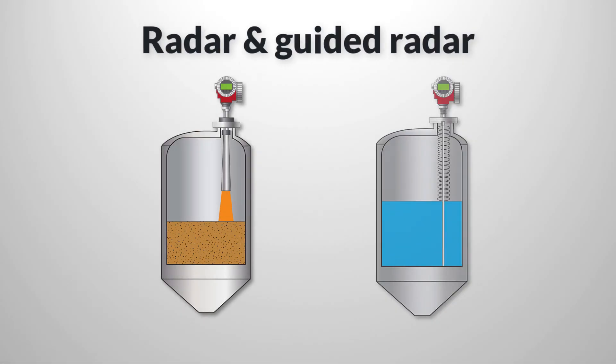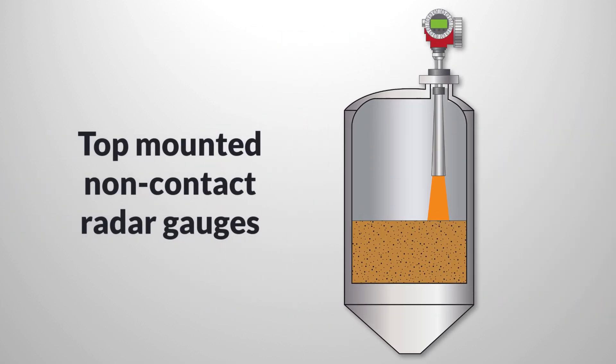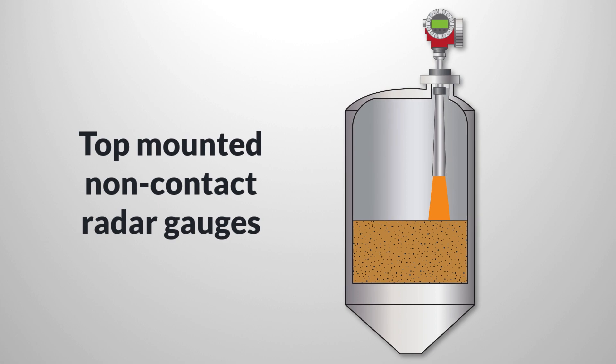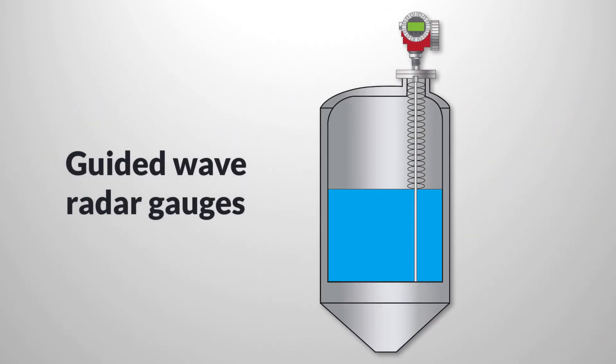Radar gauges are among the most versatile at a price. Radar gauges come in two variations. Top-mounted, non-contact radar gauges use an open-beam, reflected radar signal to determine liquid level. Guided wave radar devices are similar, but the radar signal follows a wave guide down to the material, where the surface partly reflects the signal and allows level calculation.